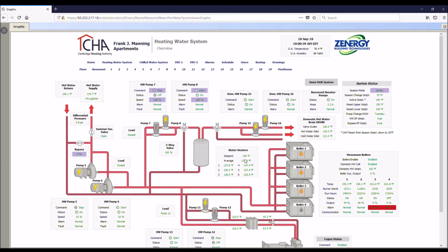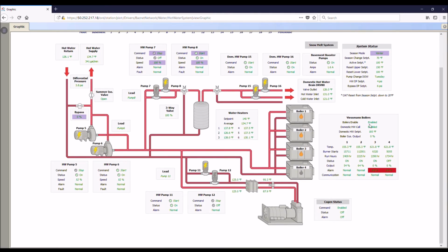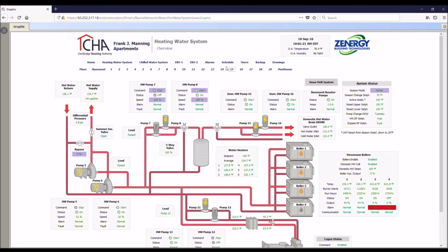So green means that is a point that we are communicating with the controller. We're going out, we're asking the controller for its value of that point, and then it sends that point back to the BMS. So green just means this point is actually residing out in a remote controller. So we're going out, asking that controller, hey, what is your average water heater temperature? And then it responds back with this value, and so we're just trying to signify that with the green color. That color will change.